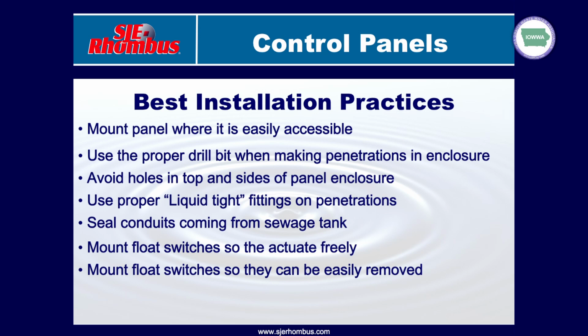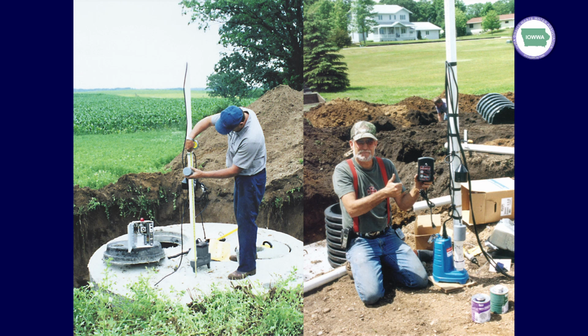So in talking about a float tree or a float bracket where we can access the floats from the top of the tank, it certainly makes service a whole lot easier 4, 5, 6 years down the road if we can access them from the top of the riser. And here's a couple of options. Here they're showing the discharge pipe and the pump being used as your float tree. That works fine. The only negative to doing it this way is that to do any service on the float switches, you also have to pull the pump out.